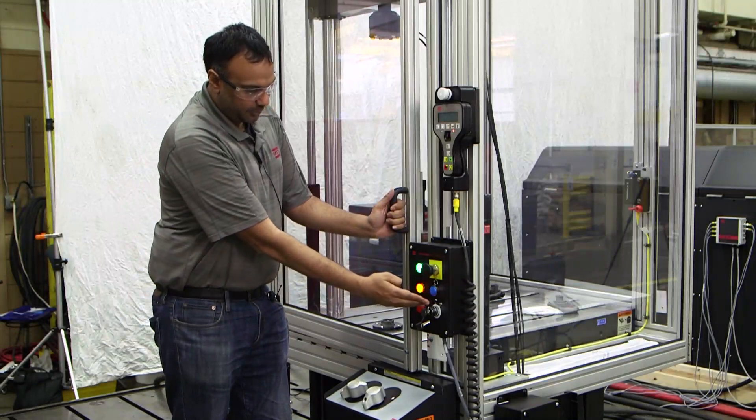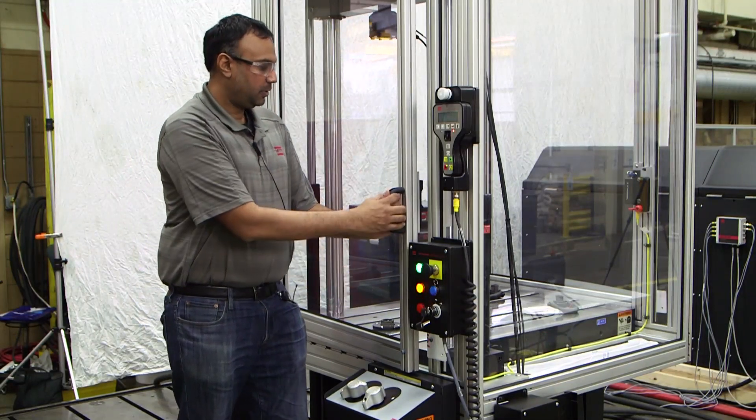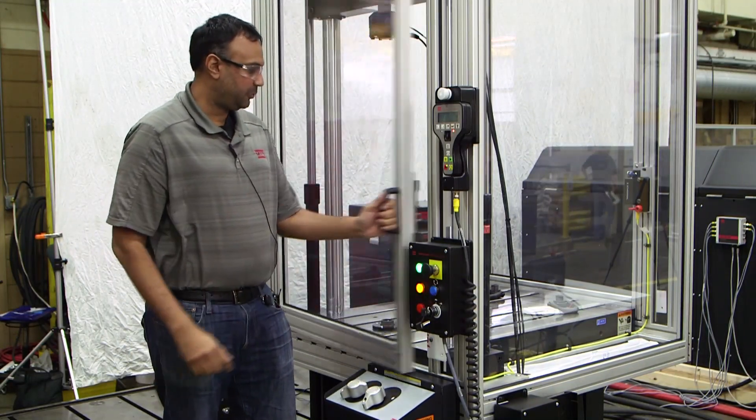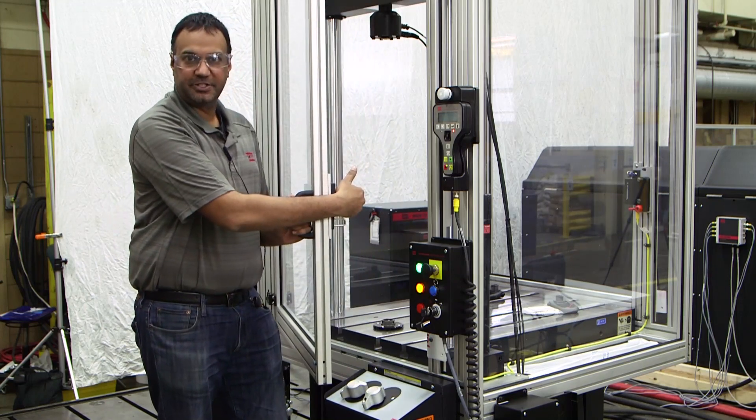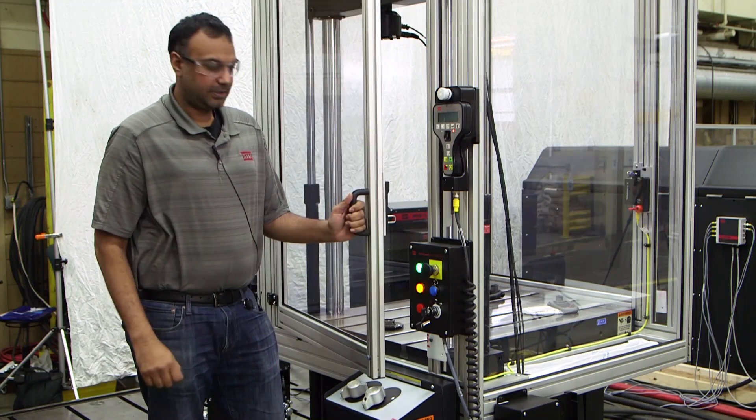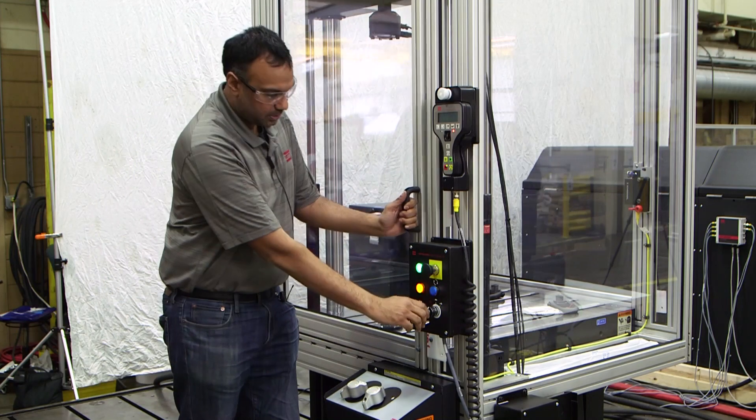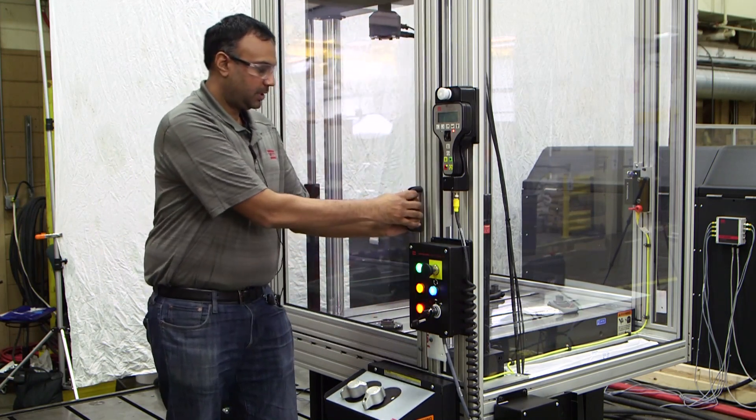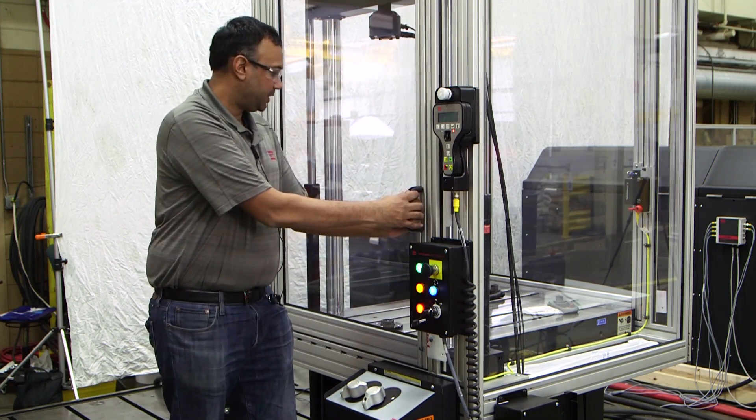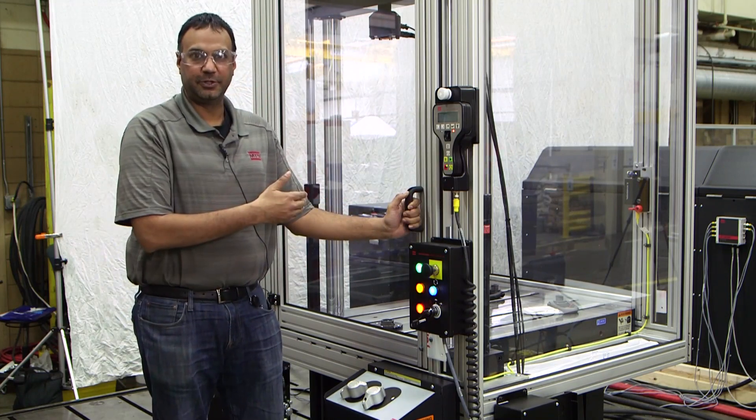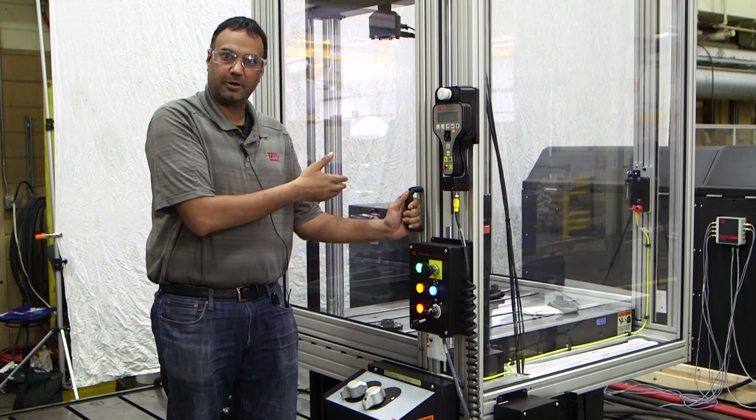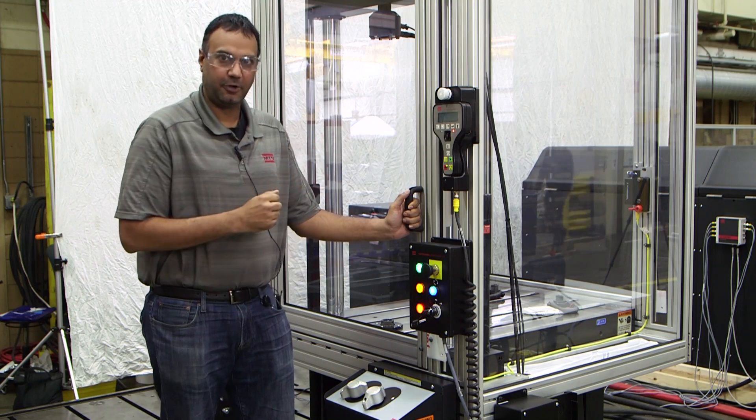For a mode switch, when we are in turtle mode, we can open and close the door as we want so we can make adjustments to the specimen or install a new specimen. Once we put it into rabbit mode, we are no longer allowed to open the door for safety reasons. We don't want anyone to get hurt when we are in high flow mode.